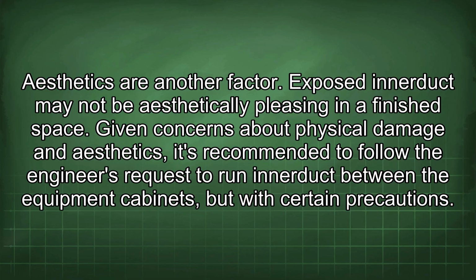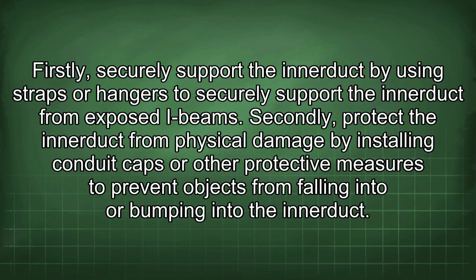Given concerns about physical damage and aesthetics, it's recommended to follow the engineer's request to run Innerduct between the equipment cabinets, but with certain precautions. Firstly, securely support the Innerduct by using straps or hangers from exposed I-beams. Secondly, protect the Innerduct from physical damage by installing conduit caps or other protective measures to prevent objects from falling into or bumping into the Innerduct.